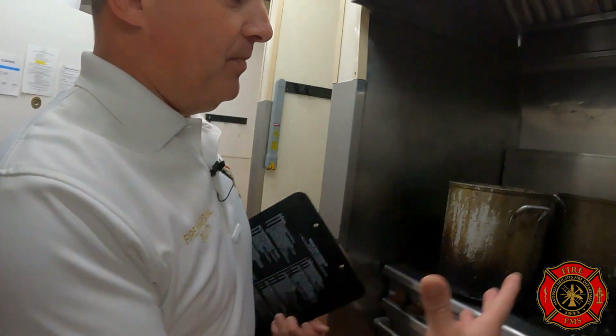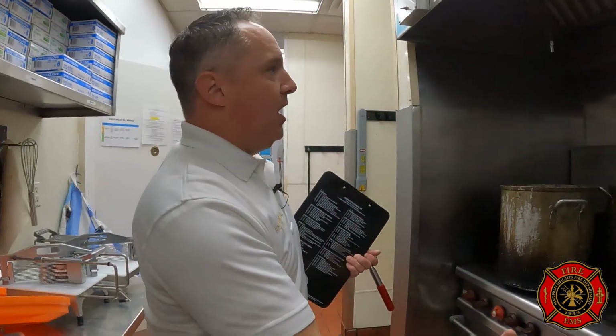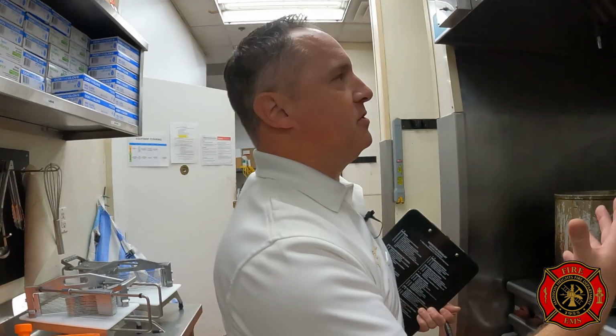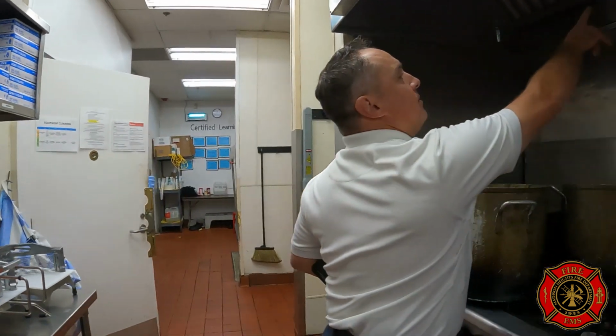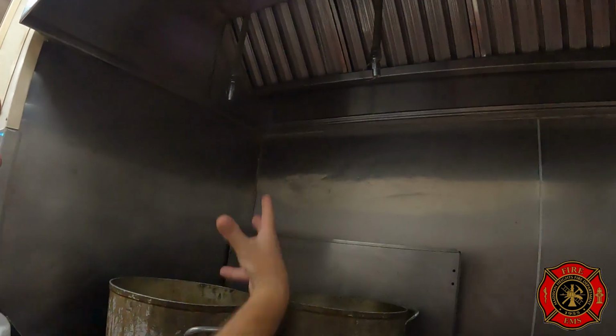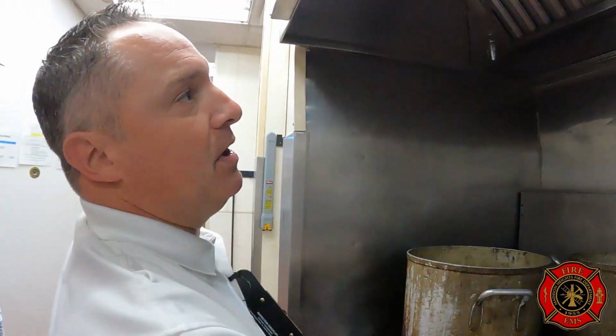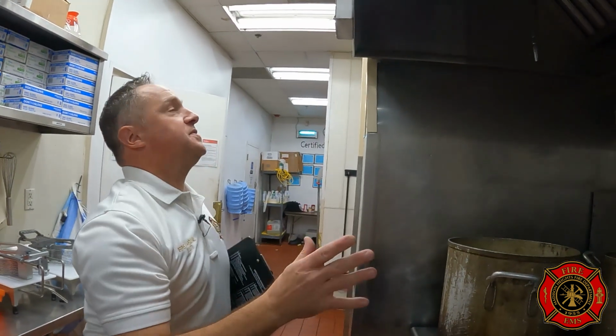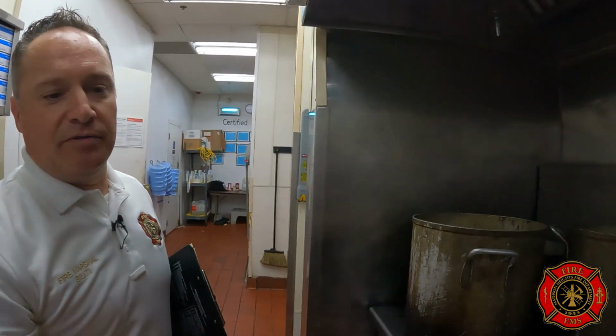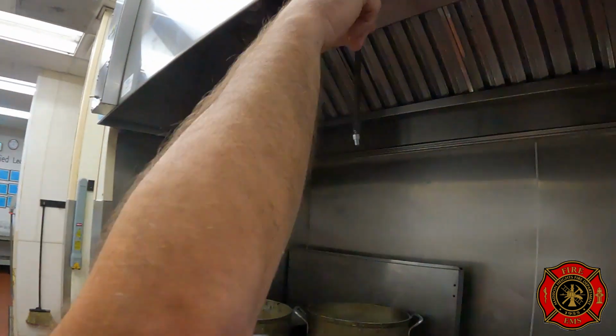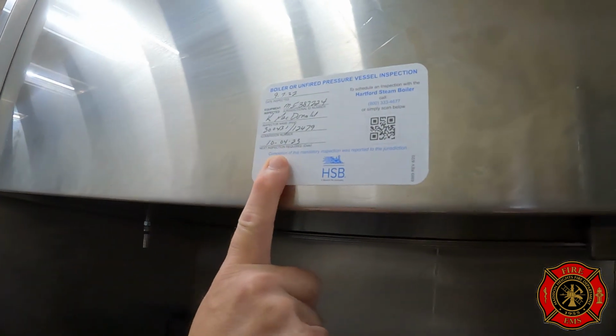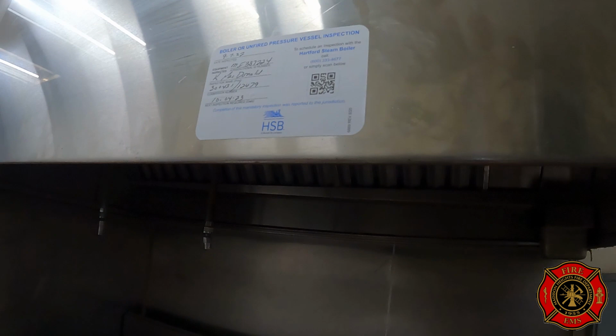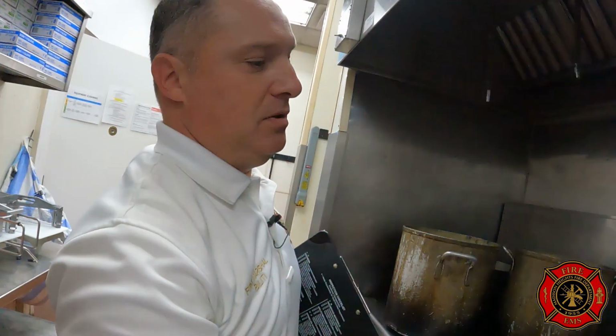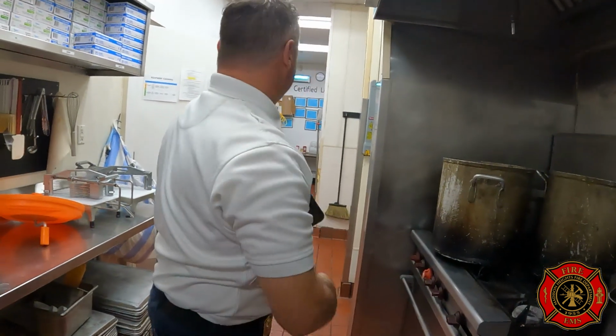So this is what I'm talking about. They have their cooking vessels here, and they have to have fire suppression underneath them. This is basically a nozzle - if there was a fire here, a chemical would come out of it and put the fire out. These systems, depending on use, have to be certified by a third party either every 6 months or every year. We take a look at this tag right here, 10/4 of 23, so it was just done a week ago. They're well within where they need to be.